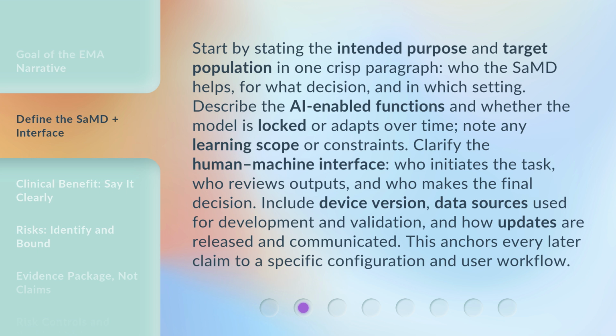Clarify the human-machine interface: who initiates the task, who reviews outputs, and who makes the final decision. Include device version, data sources used for development and validation, and how updates are released and communicated. This anchors every later claim to a specific configuration and user workflow.